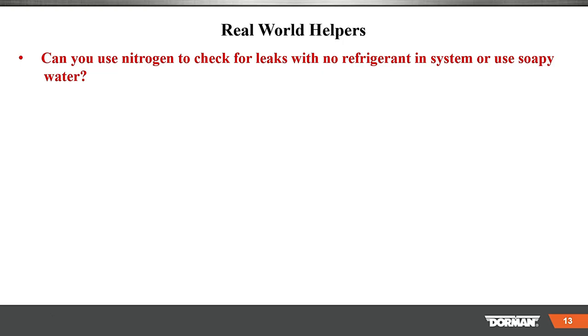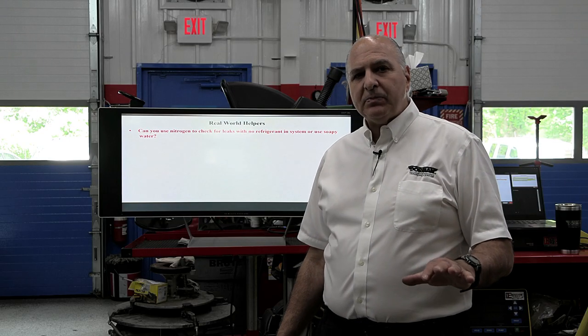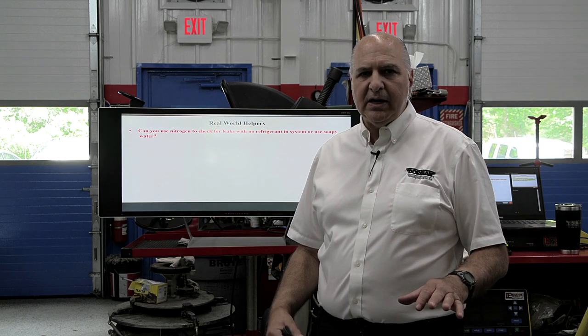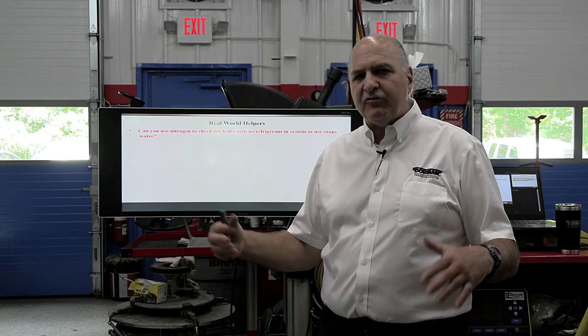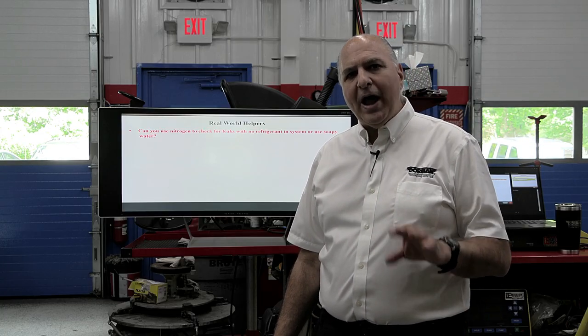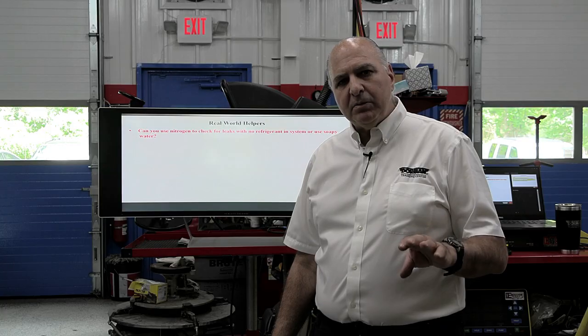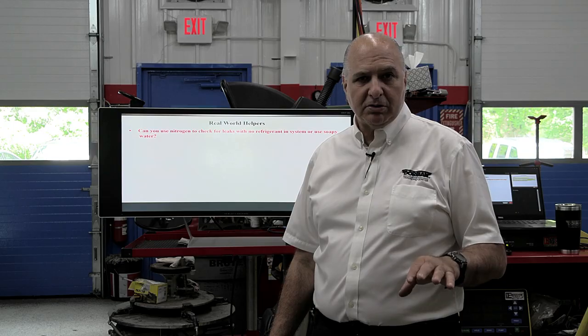Now, when you go checking the system for leaks, don't think that vacuum is totally different than pressure. Of course, in the industry they say, oh, if it holds vacuum for a mandatory 10 minutes, the system has no leak. Big lie. There is no way that vacuum is telling you there's no leak.